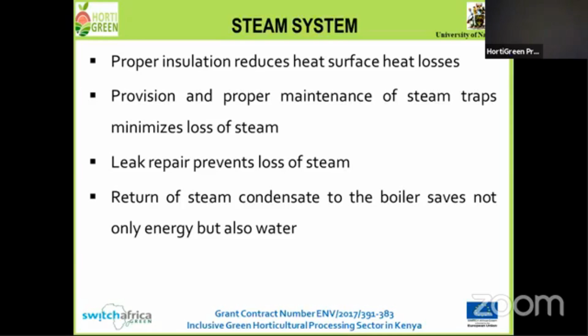Steam traps are installed on the steam distribution line after the equipment that is utilizing the steam, so that only the steam condensate is returned to the boiler. So a steam trap does not allow steam that is unutilized to escape. And leaks, of course, are obvious. These should be prevented. And I've already said that the condensate should be returned to the boiler.